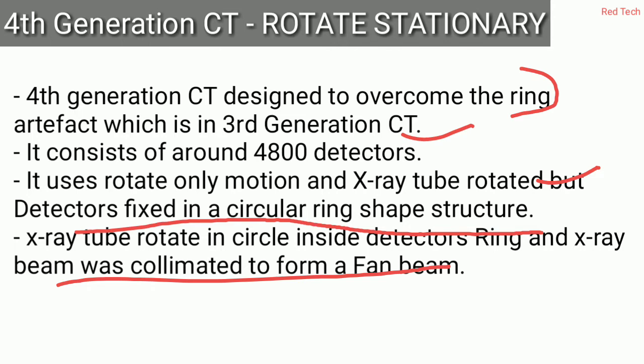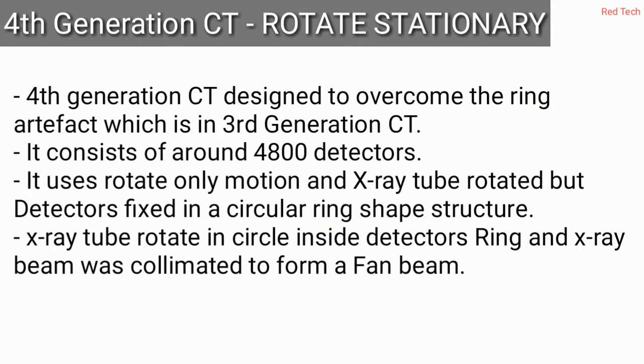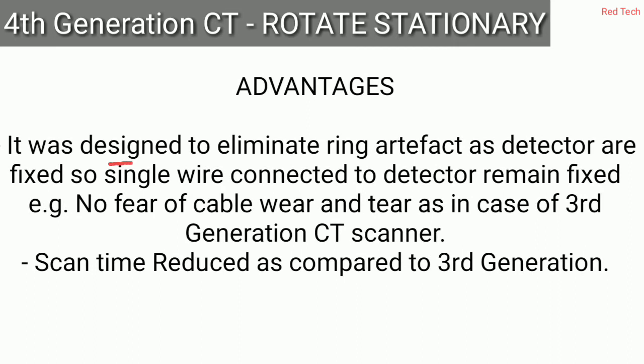When the X-ray tube emits X-rays, they penetrate the patient and are absorbed by the detector array, which is fixed in a circular ring. To summarize: fourth generation CT was developed to overcome the ring artifact, 4800 detectors were used, and only the X-ray tube rotates.